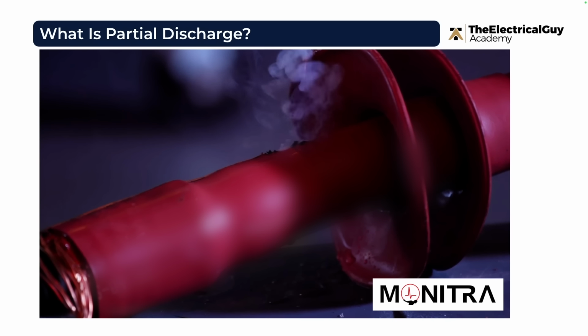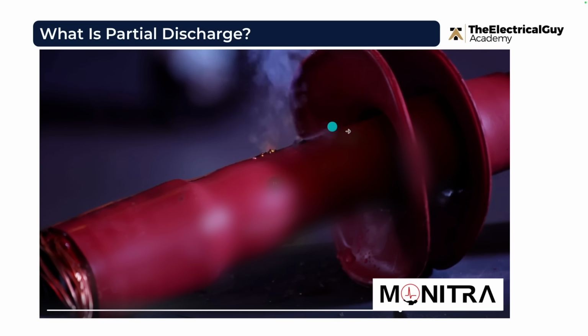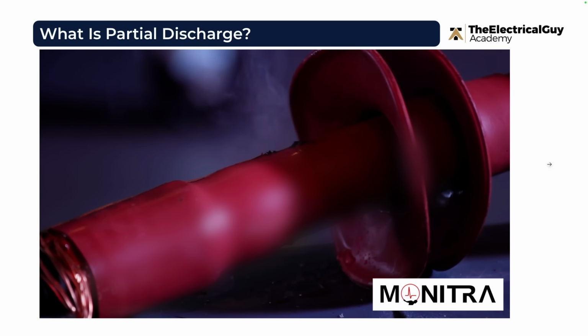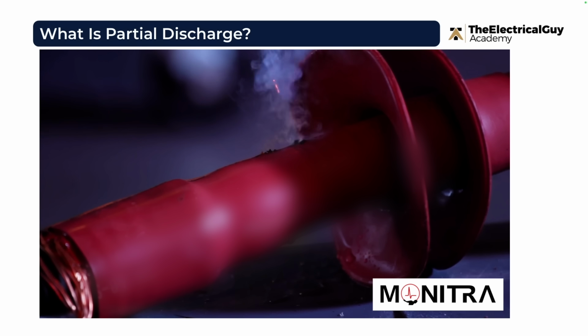Let me actually show you one actual video of partial discharge. So this is a cable, and you can see that because of the voids there, electrical discharge has started coming out. Now, is it breaking the whole insulation? Not yet. It is only happening partially. And that's why the name partial discharge.